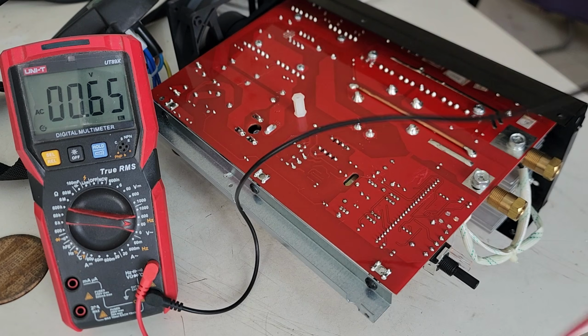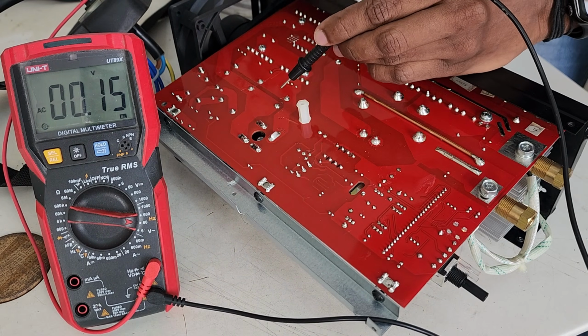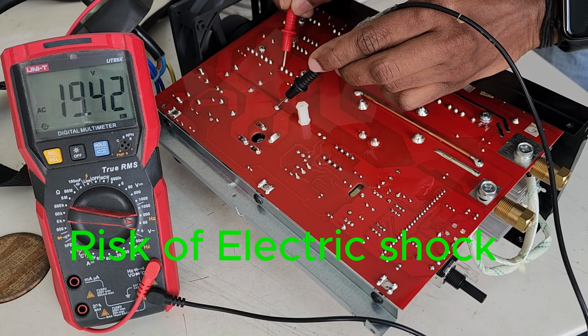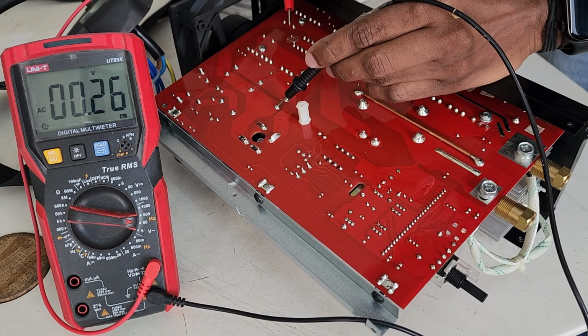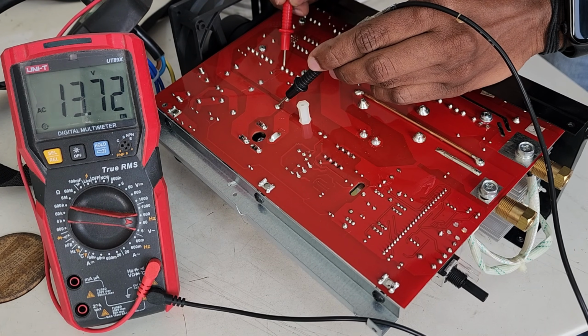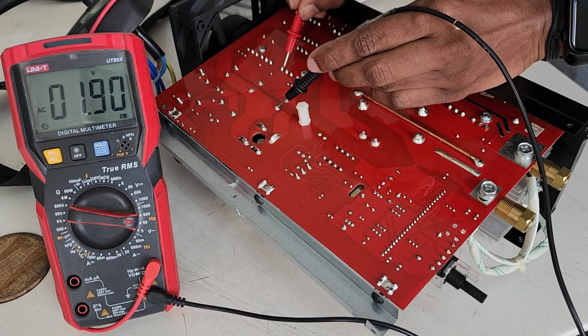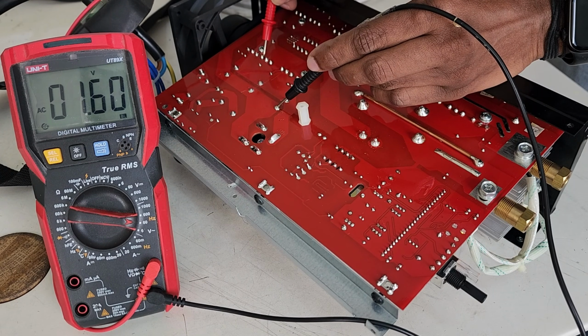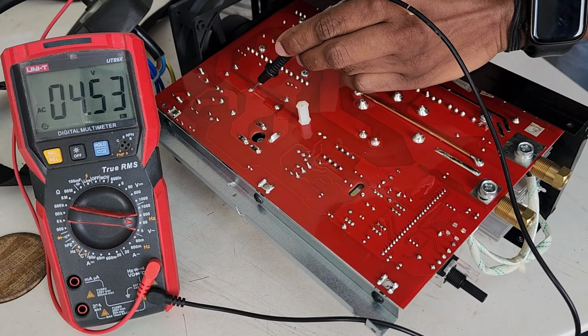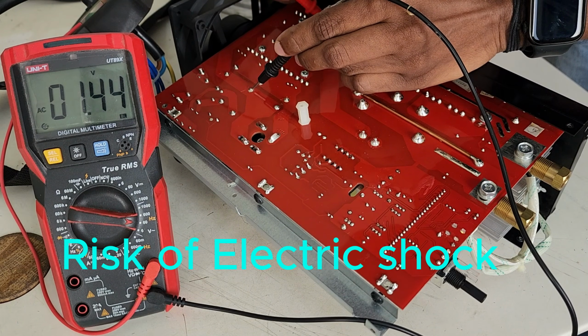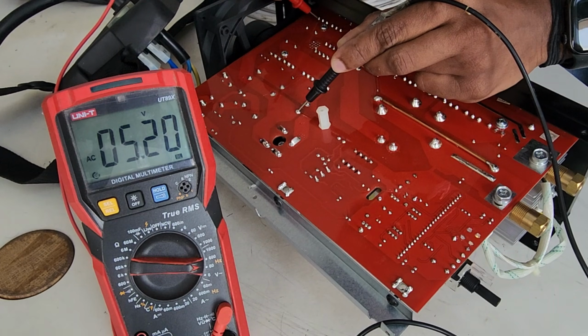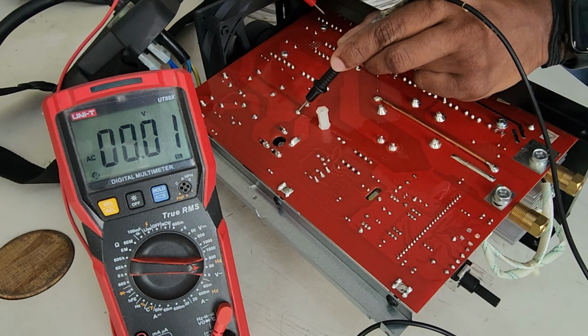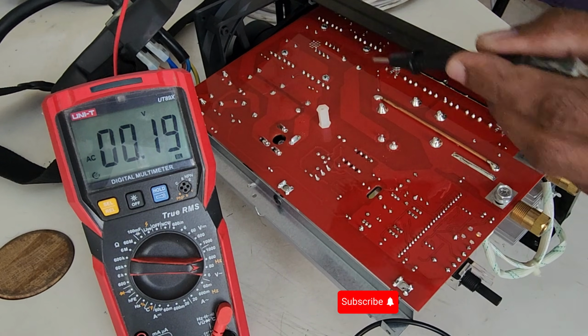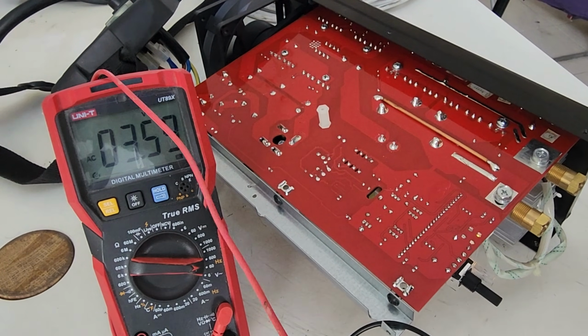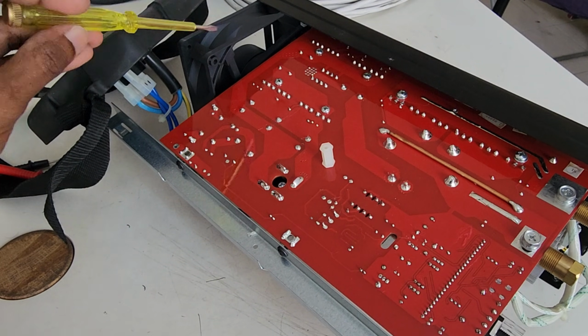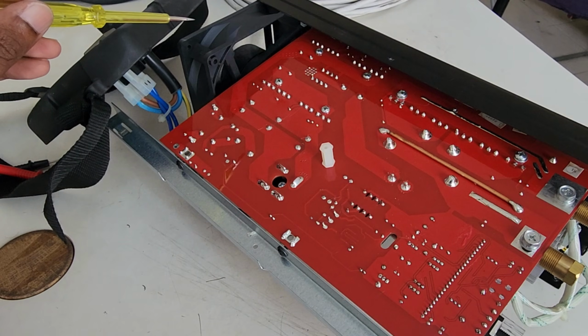Let's measure the gate voltage of the IGBTs. In order to check the gate voltage, connect the multimeter common lead to negative and positive lead to gate of the IGBTs. The gate voltage is very low, it should be minimum 5 volt. So here no gate voltage is generated. Now we have to check the inverter module section. Now let's turn off the mains voltage. We have to discharge the main filter capacitor in order to avoid electric shock.